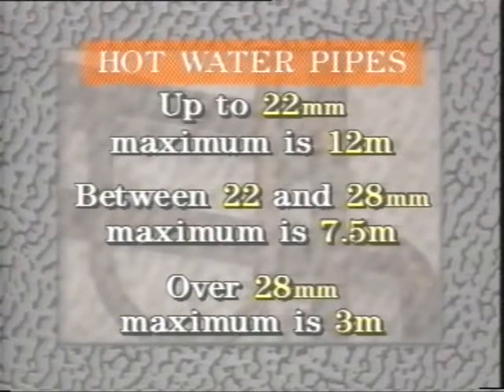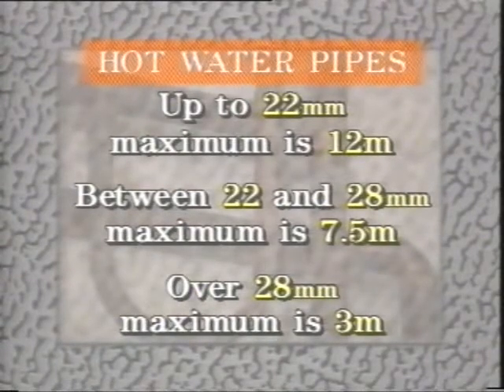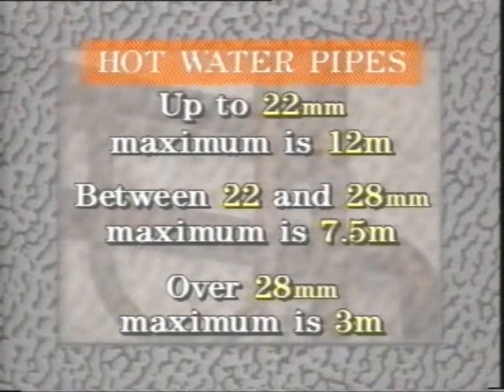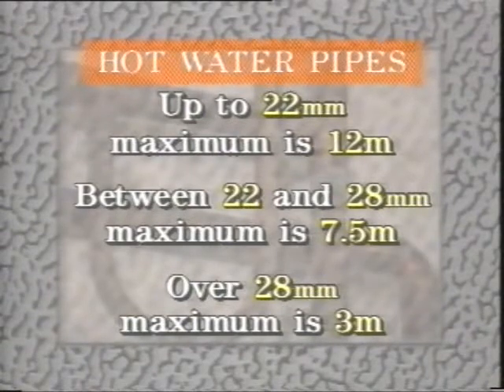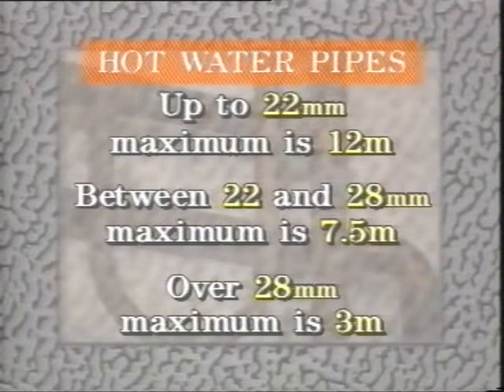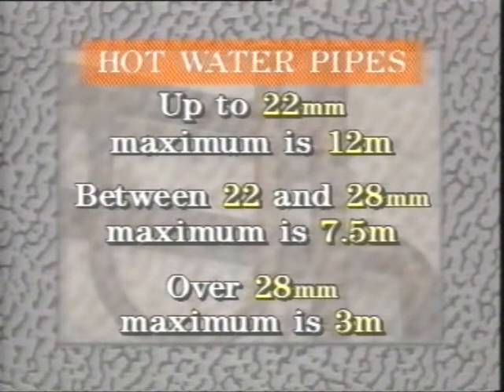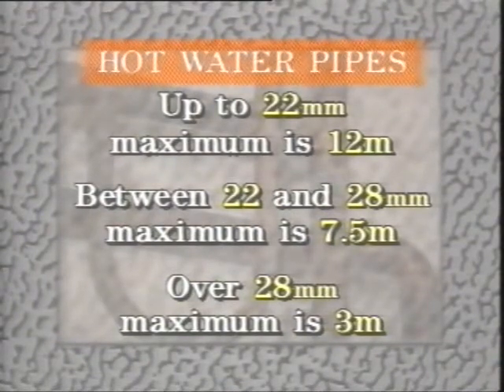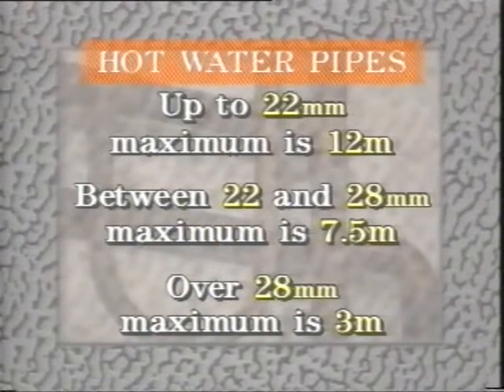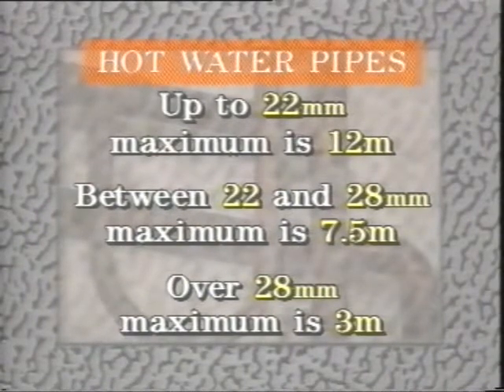If hot water draw-off pipes are too long, they're obviously going to lose a lot of heat. Keep them as short as possible. For pipes up to 22 millimeters in diameter, the maximum length is 12 meters. Between 22 and 28 millimeters, it's 7.5 meters. And over 28 millimeters, the maximum is 3 meters.